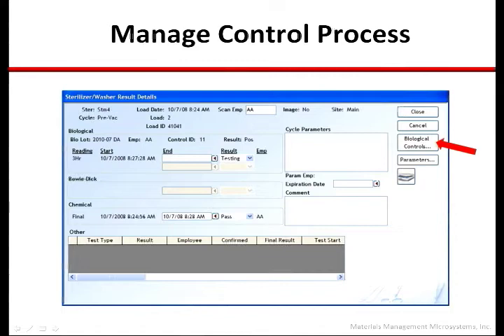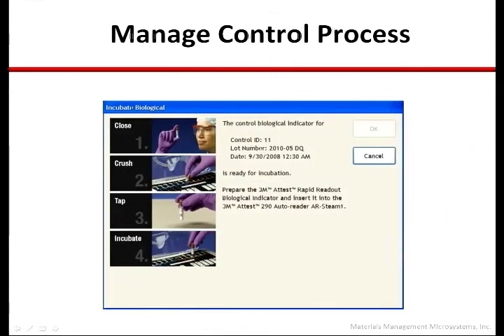Further, the system will correlate test BI lot number to ensure spore viability and will provide prompts and disciplines based on recommended practices and instructions for use. Instructions for use for control BIs will be provided with a prompt to place the control into an available well in the same auto-reader. If the control is inadvertently placed in the wrong auto-reader, it will be detected as such and the technician will be guided through the correction sequence until the situation is resolved. If everything is in order, the system will confirm that the process will be completed pending results.